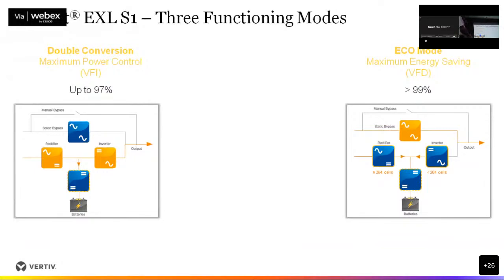The difference between these two modes: here with the latest technology we are able to achieve 97% efficiency, but here it is 99%. What is the difference apart from this? The load disturbances are all exposed to the utility here, because you connect all your load directly with raw power. Whereas here in UPS, the load is always connected to the inverter, and the inverter protects the load.